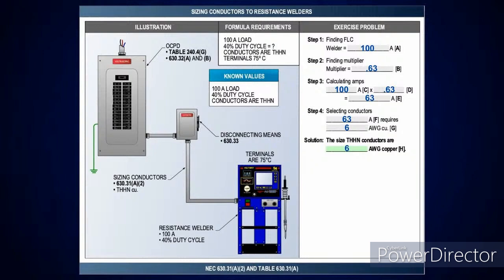All other motors were taken at 100%. I got an AC unit, use the nameplate value. You take 125% for the largest single motor. If you had multiple motors, all the rest are taken at 100%. And then when I get here to welders, everything is taken by the nameplate of what the welder is, and then you get the multiplier and size your conductors. Pretty simple. Right. True. All right.